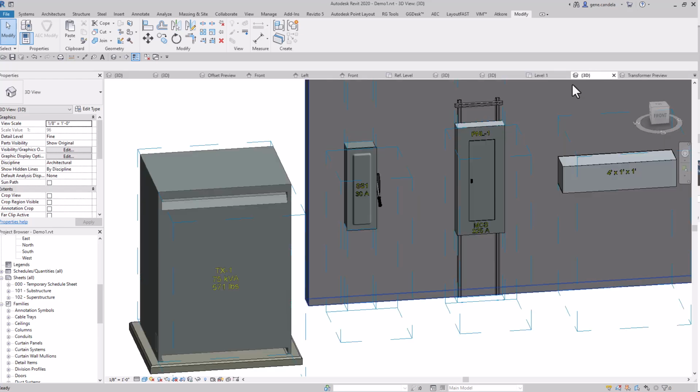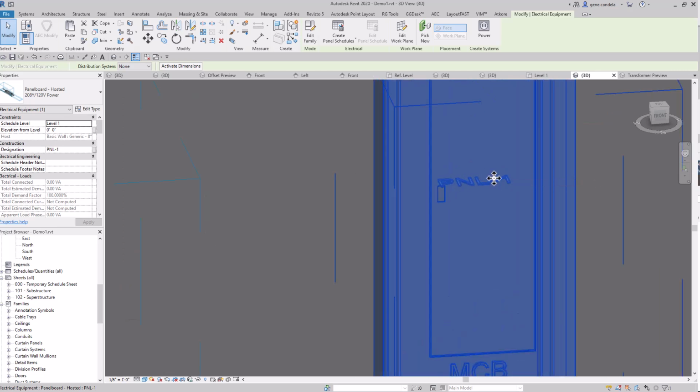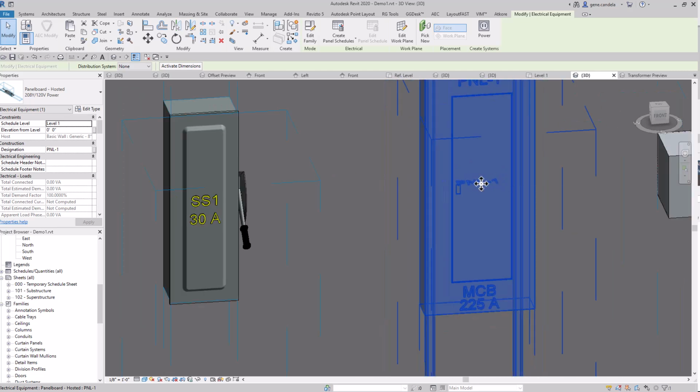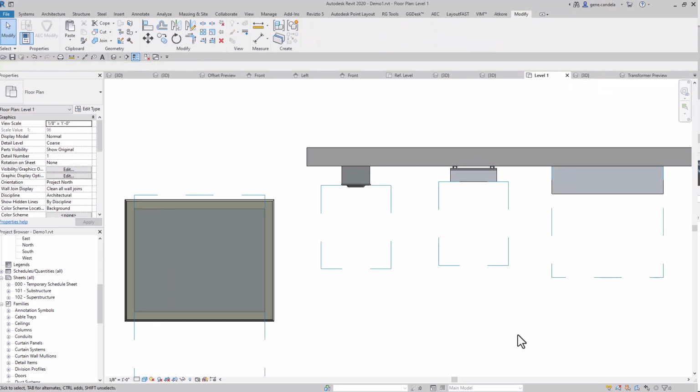Another thing I also do is, as you can see here, when I'm wiring things up, you can't see the designations. But in the 3D view you can see it, like here, for example. I put the designation inside the panel. So when you're looking at it in plan view, of course, it's not interfering with your conduit placements or anything like that. But as soon as you hover over it, it tells you what the designation is. And here I have the kVA in here. To me, it's a big help. It doesn't get in the way of the conduit.